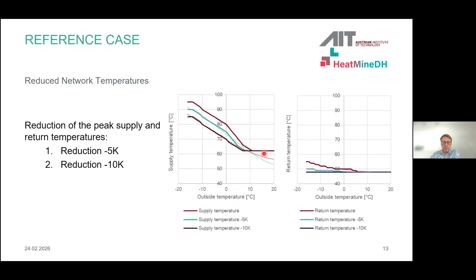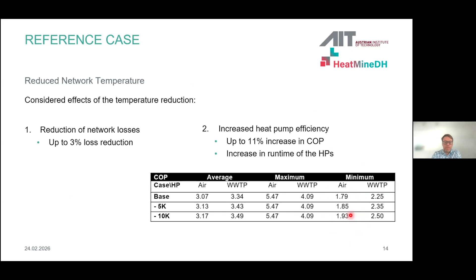This has two effects. One on the network losses, which decrease by up to 3%. And the second effect is the increase in heat pump efficiencies. The COP of the heat pumps will increase by up to 11%. You can see it here, especially in the minimum COPs. In the winter months, we have an increase in the COP for the air heat pump and also for the wastewater treatment plant heat pump.